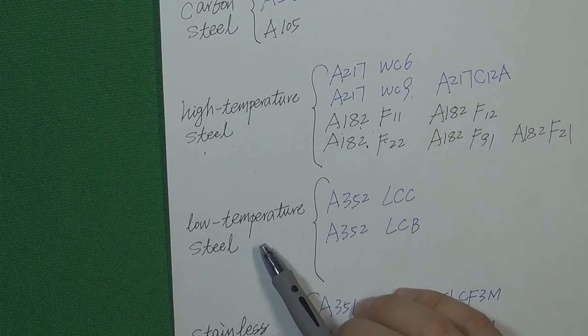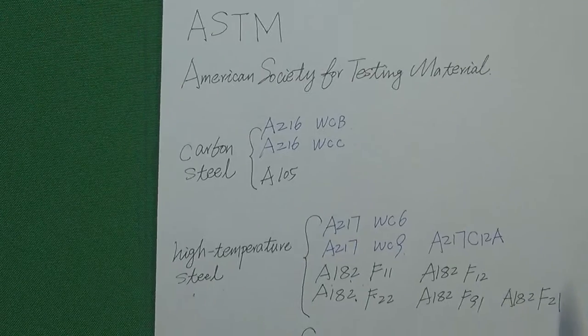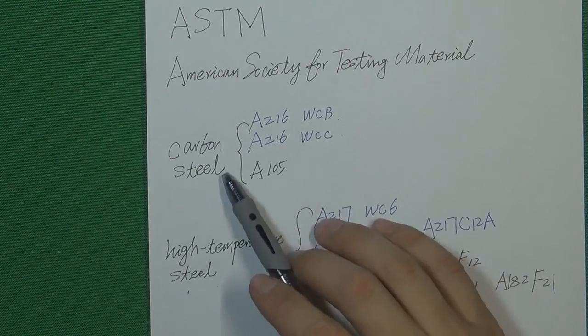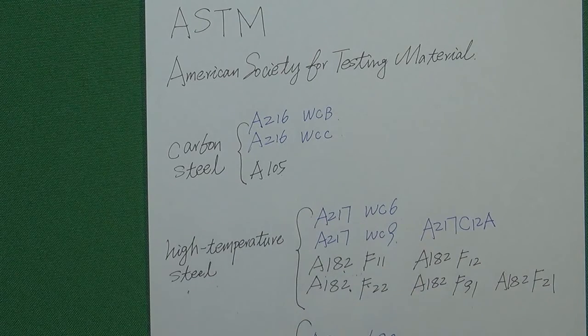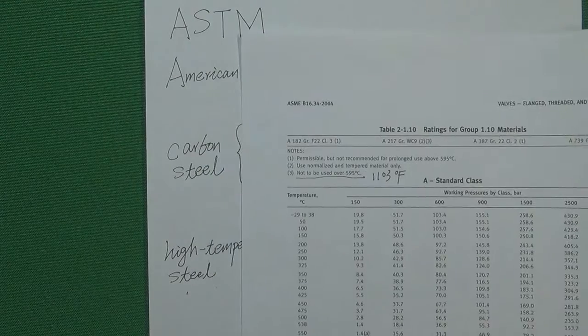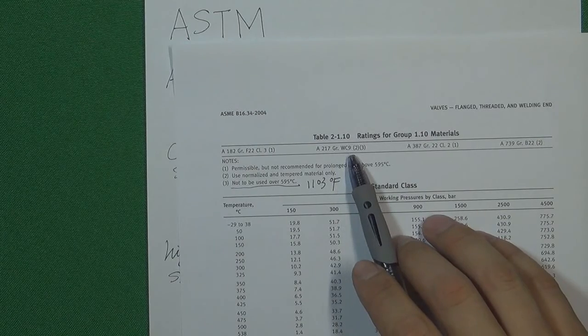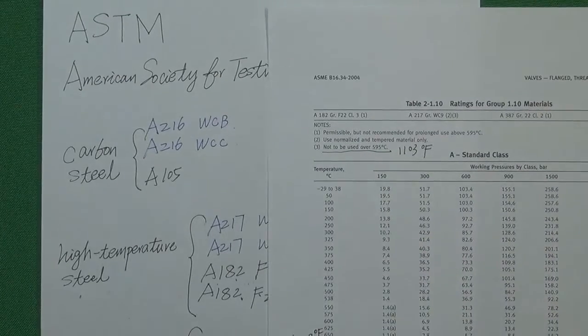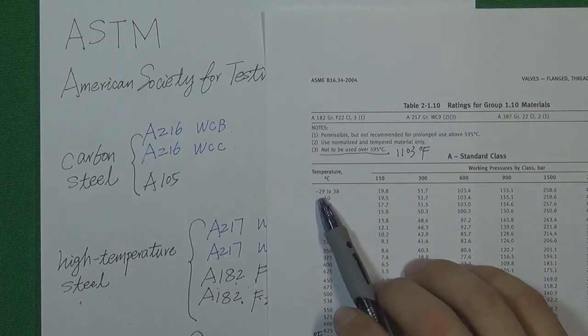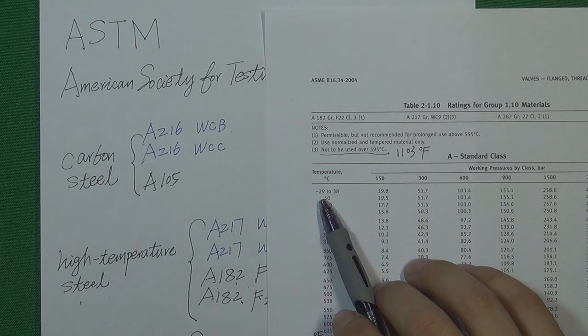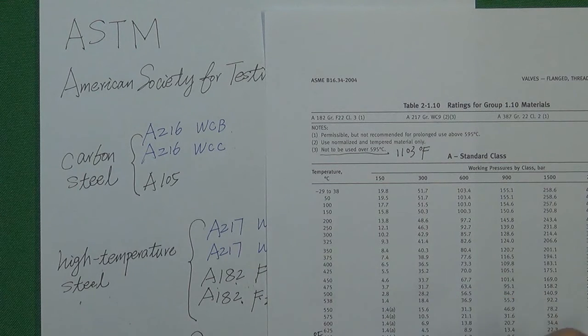Before we talk about the low temperature steel, let's look at what is the minimum temperature for carbon steel and the high temperature steel. According to the standard ASME B16.34, the high temperature steel, for example the WC9, this kind of material can only work in a minus 29 Celsius degree environment, which equals minus 20 Fahrenheit degrees.